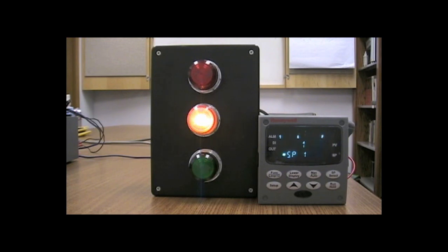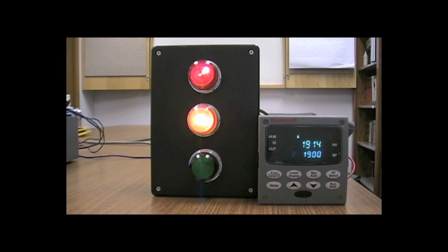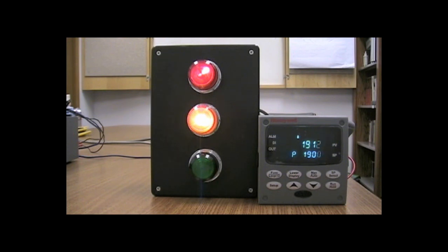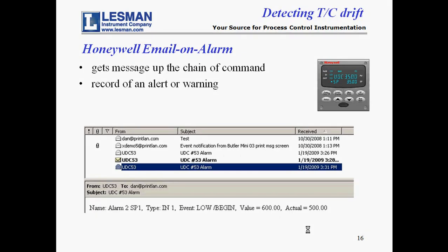Now watch what happens when I insert an additional 100 ohms of resistance into the circuit. The red lamp turns on, telling us that the thermocouple is in really bad shape and is near failure. The yellow lamp stays on because the loop resistance is way above its set point. The number two LED alarm indicator in the upper left corner of the display turns on. Eventually the lower display will say TC1 FAIL, indicating that the thermocouple is near failure. The controllers can also send an email on alarm, which is one way of making sure that the message gets up the chain of command. The slide shows an Outlook Express email message sent from a UDC controller.